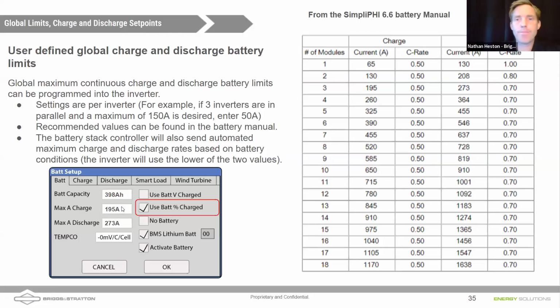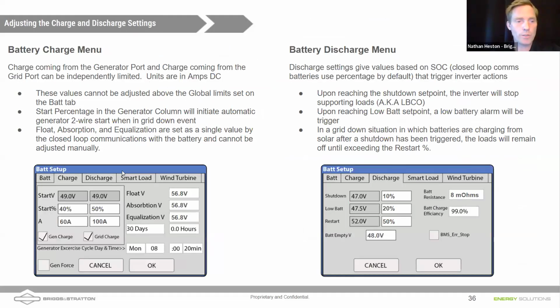The recommended maximum continuous charge and discharge ratings come in a table in the 6.6 battery manual. It's 195 for a single stack, and the maximum discharge is 273 for a single stack. Though I will point out, if you're using a Sol-Ark 15K, the Sol-Ark 15K is only capable of 250. So the batteries are capable of a little bit more there. At 48 volts, Sol-Ark 15K will be limited to 250.